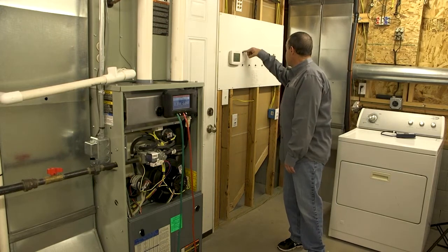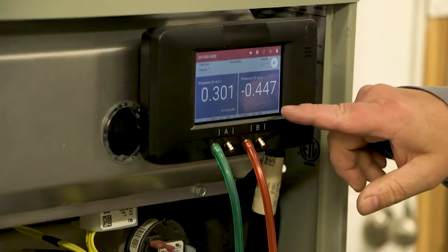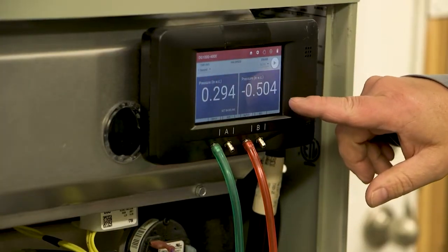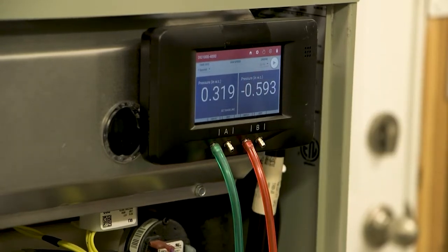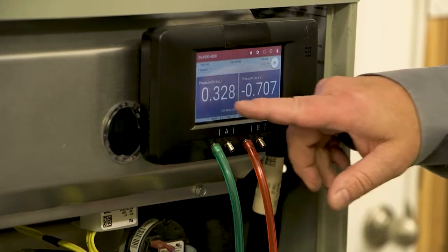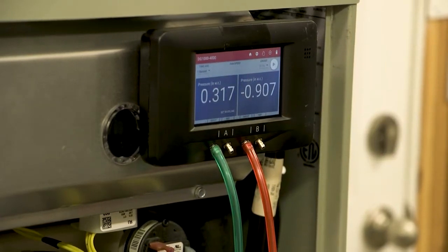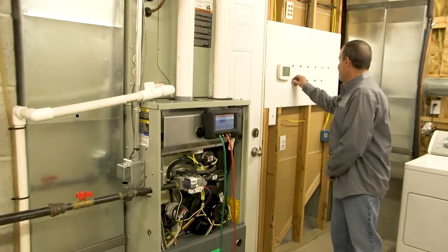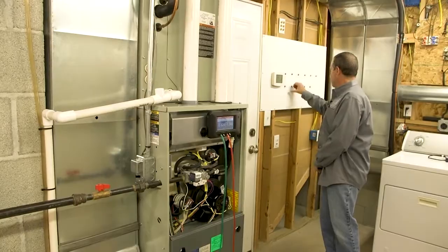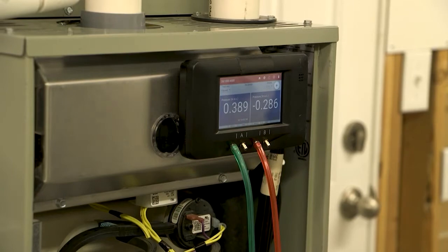So go ahead. Okay, you can see my static pressure, or my blood pressure, starting to skyrocket. You can hear the blower motor is working much harder, which is not good. It's consuming much more electricity. Our static pressure is getting into a very scary zone where it can actually cause damage to the system. So before the system explodes, I'm going to go ahead and fix that. You can hear the blower motor ramp down, and you can see the static pressure start to come back down.